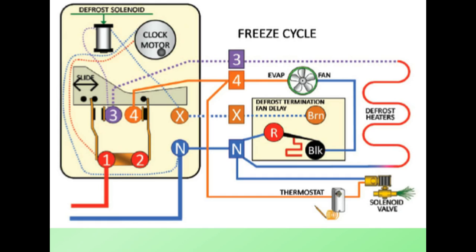All right, let's break this defrost cycle down step by step. There are some differences here in the way the defrost works in refrigeration. In air conditioning, we're used to having our power controlled by opening or closing of contacts and switches. When we are looking at defrost, not only do we open and close to apply and disable power, we also have some controls that make or break the neutral to some loads.